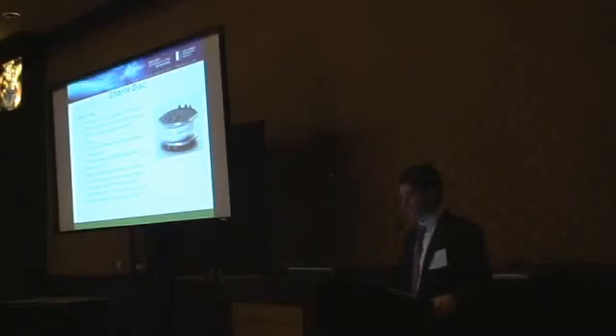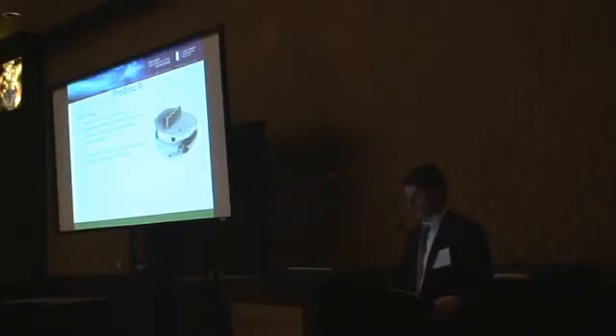There are multiple different design flaws that I won't go into in great detail, especially since the Charité is not even on the market anymore, but they don't really match the vertebral end plates very well. The fixation between the metal and bone is inadequate. The polyethylene core is problematic. ProDisc, similarly, the spacer is non-linked, has a dome shape that articulates with the metal cup, and the center of rotation is placed anteriorly such that it significantly loads the facets and causes pain and more problems.